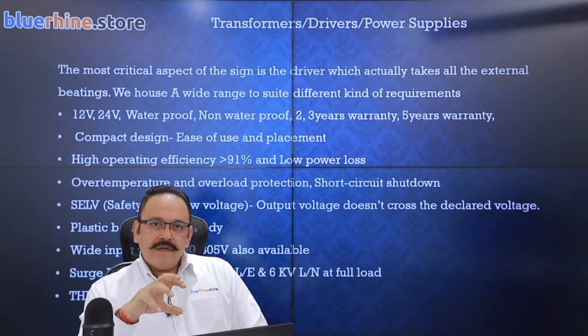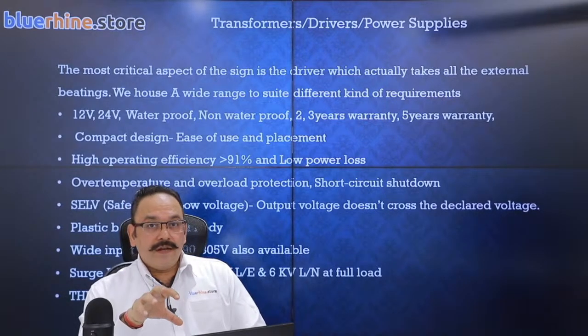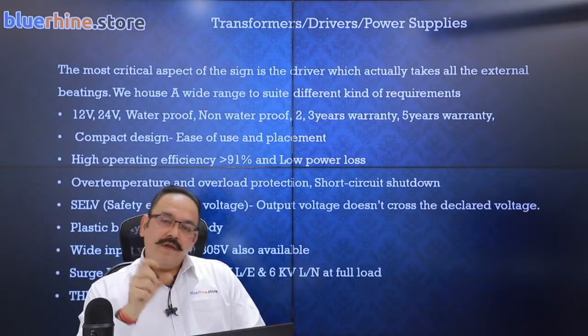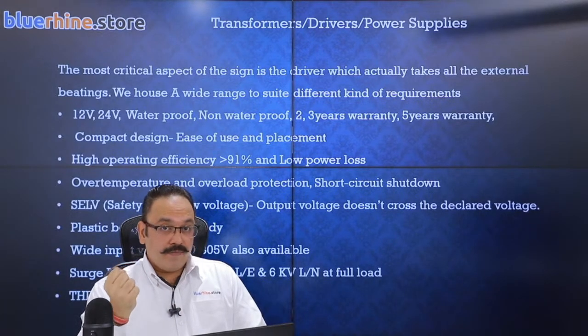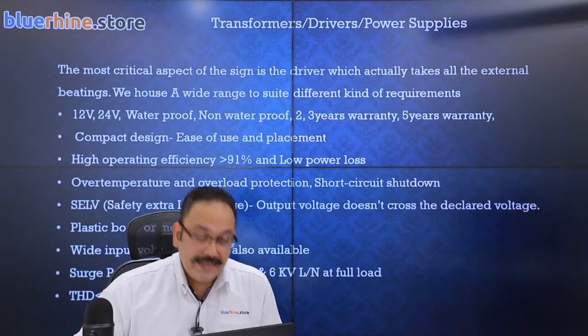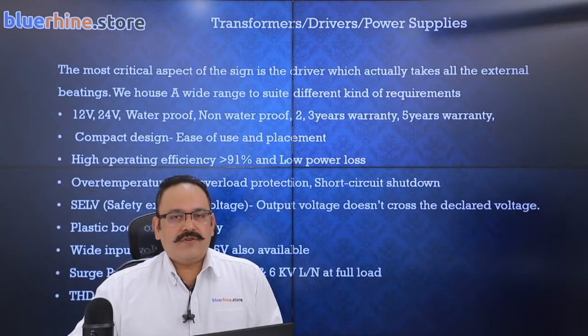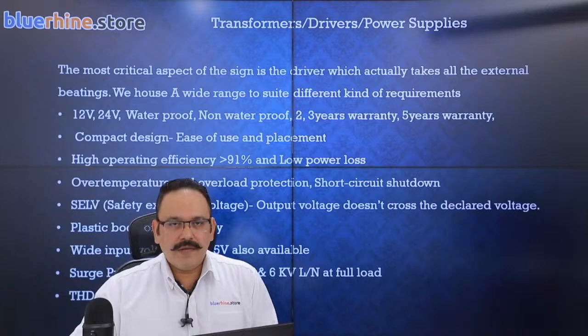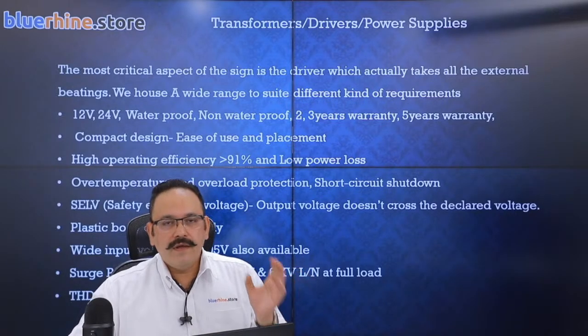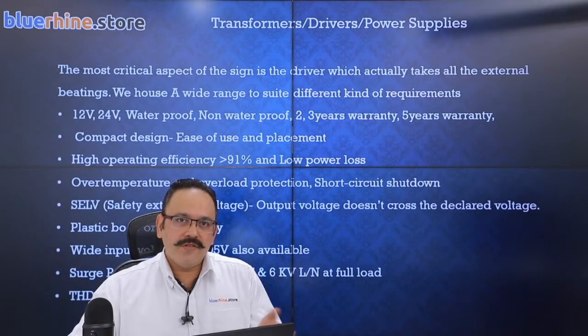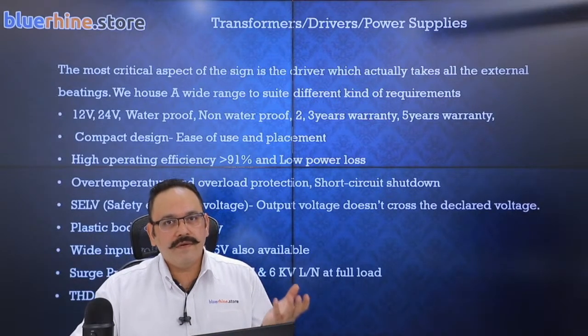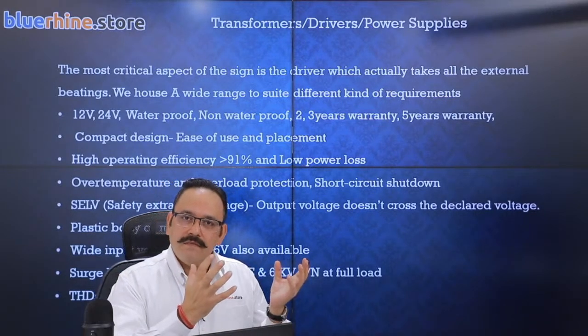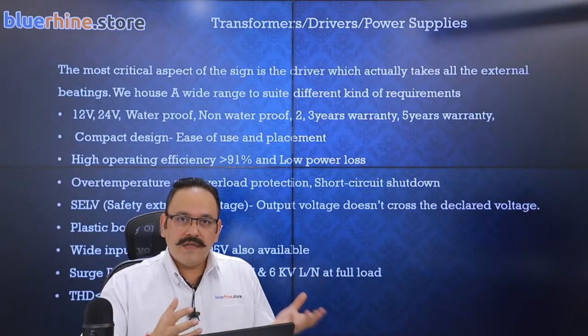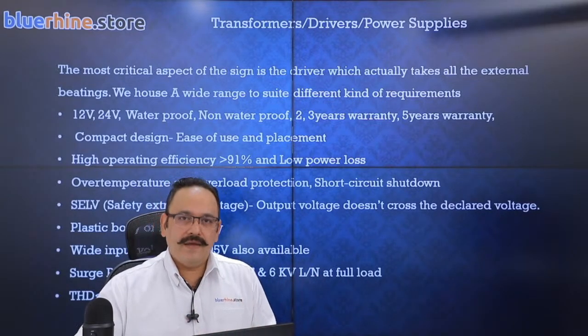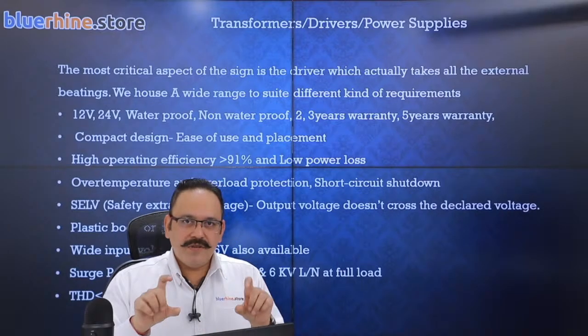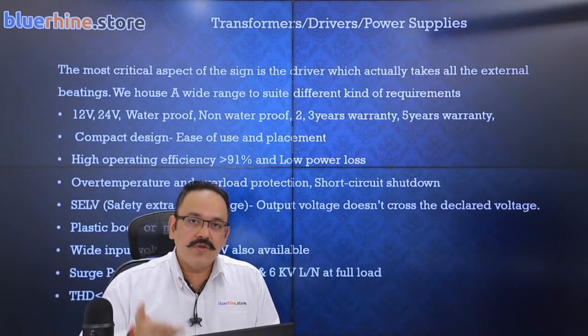In the Middle East, certain factors definitely affect power supply performance - I'm talking about high temperatures. Middle East conditions are very hot, and when inside a box the transformer is practically roasted. In a remote location the ambient temperatures are already very high, and with an airtight or watertight box, the temperatures inside are even higher. So the case temperature of the transformer goes up.